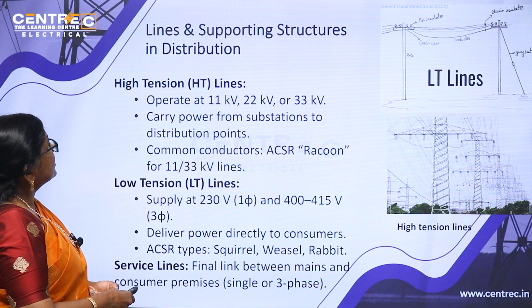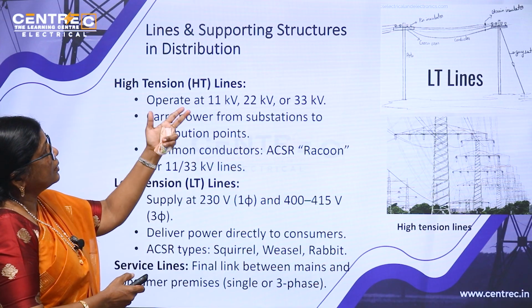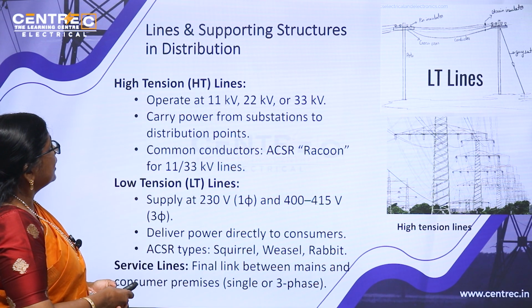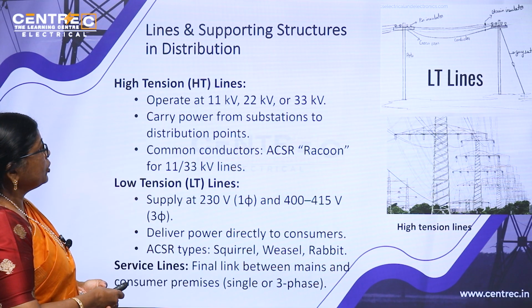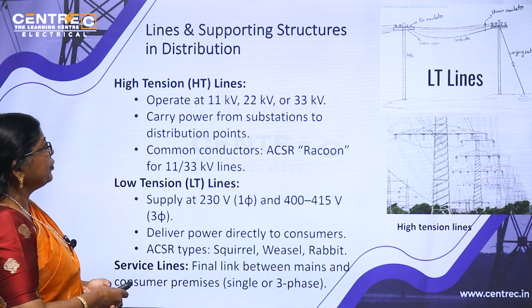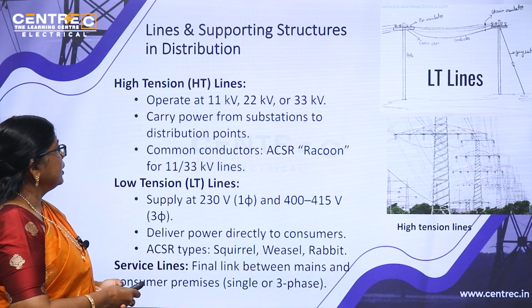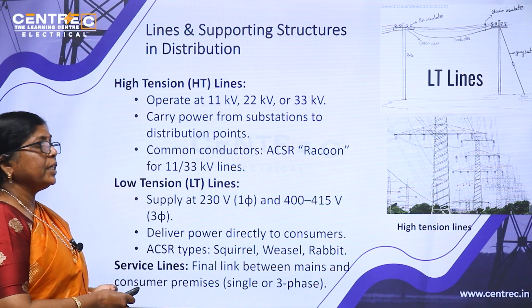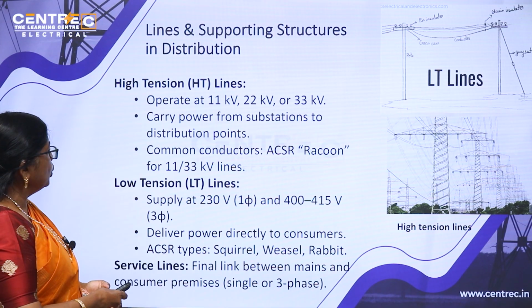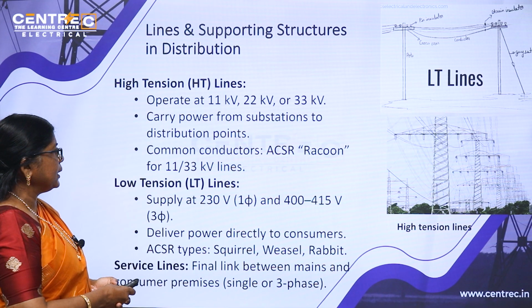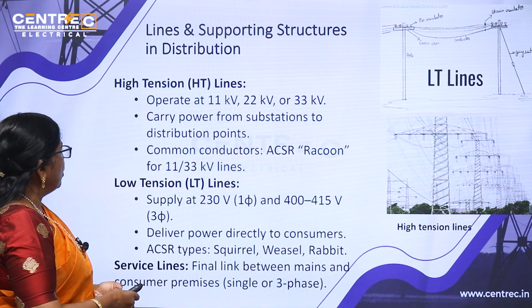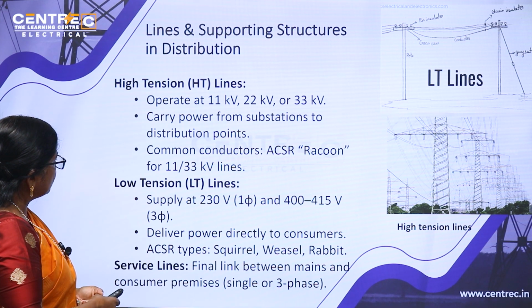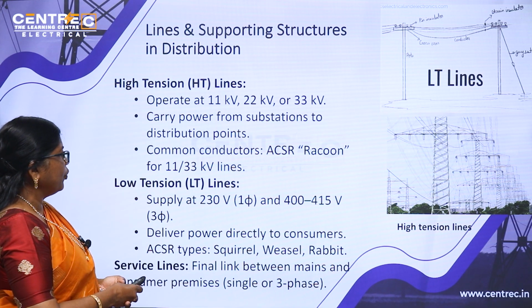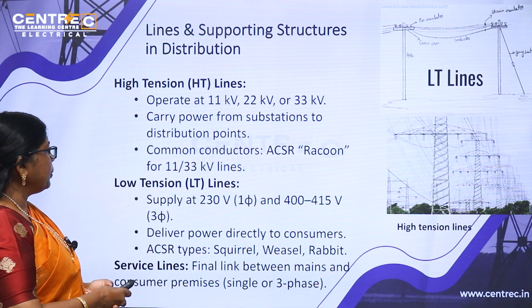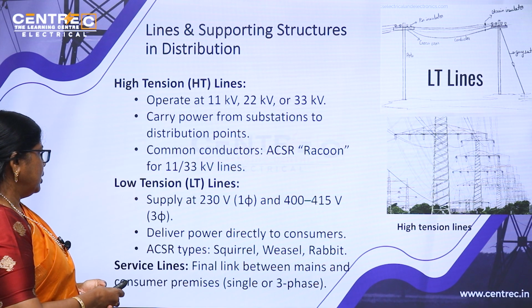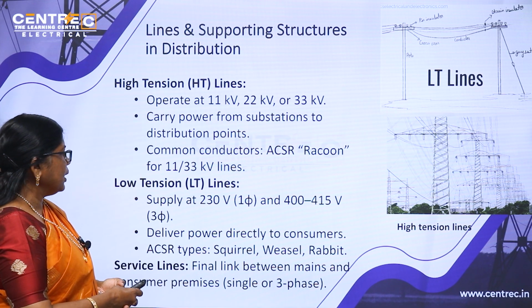Lines and supporting structures in distribution. We have LT lines like this, and high tension lines operating at 11 kV, 22 kV or 33 kV, carrying power from substation to distribution points. Common conductors are ACSR, aluminum conductor steel reinforced, raccoon for 11 and 33 kV lines. And low tension LT lines supply at 230 volt single phase and 400 or 415 volt 3-phase, delivering power directly to consumers. Then ACSR types: squirrel, weasel, rabbit.